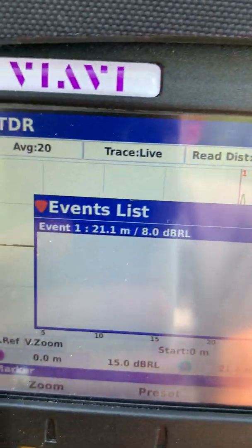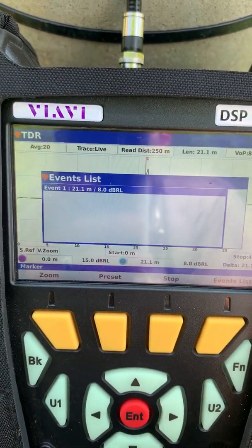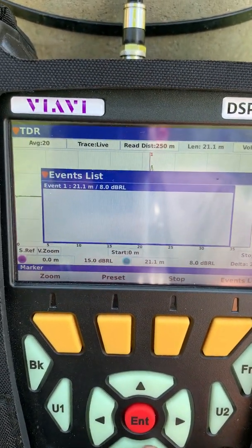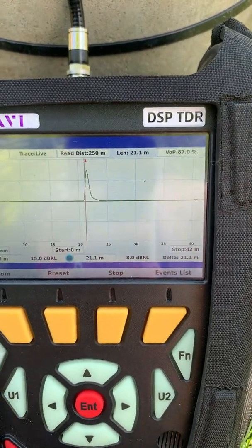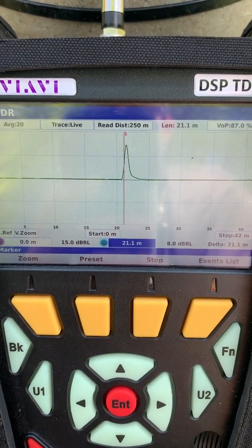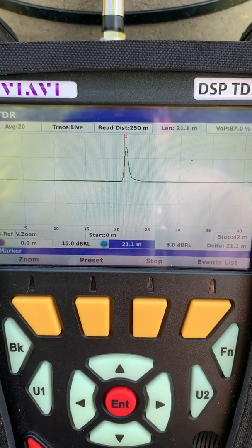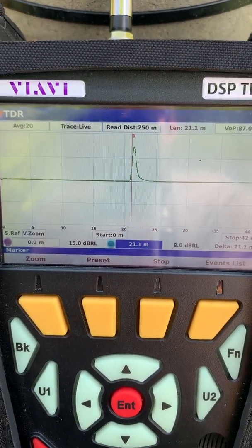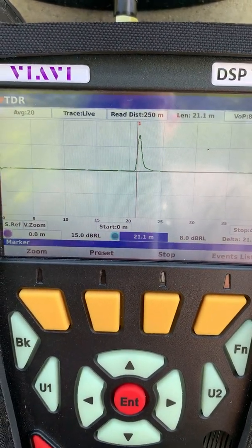The dBRL reading will change slightly too as you TDR — it won't always be exactly the same. With a VOP of 87%, our distance reads 21.1 meters. Making sure you have the proper VOP is important, especially when you're digging for cables and want to locate the fault as closely as possible. Those are some tips and tricks — have your meter pre-set with user profiles, go into TDR, hit start, then hit Events List, and you'll see all the events showing where your faults are.